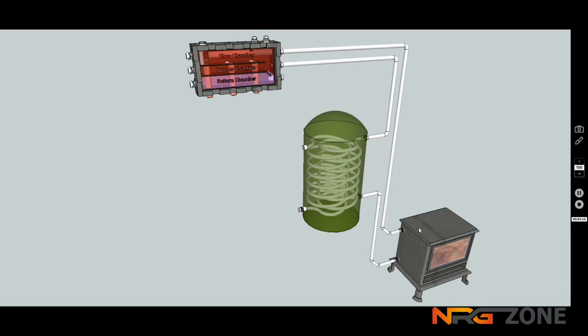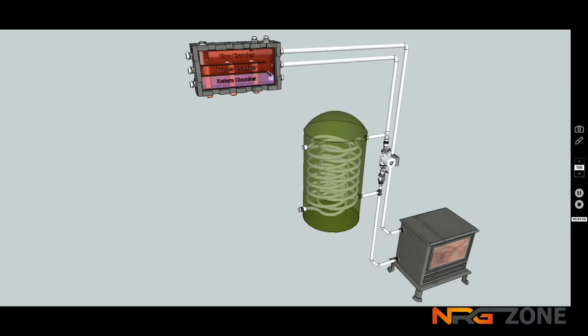If the stove output is not so great, this would probably work fine. If you do need to introduce a pump on the stove, then very simply, this elbow could be removed, and this elbow could be removed. And then, in that instance, you could introduce an injector pump. Therefore, you'd have a conventional T here, and an injector T here, with a non-return valve here.